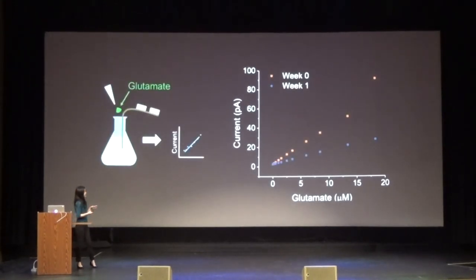In this example, looking at the calibration curve on the right, I measured the response at week zero, shown as orange squares, then soaked the device in a solution for one week and measured the same device again, shown as blue dots. Even after only one week of soaking in the chemical solution, you can notice that slope, or line, starting to get flatter, a little more horizontal.